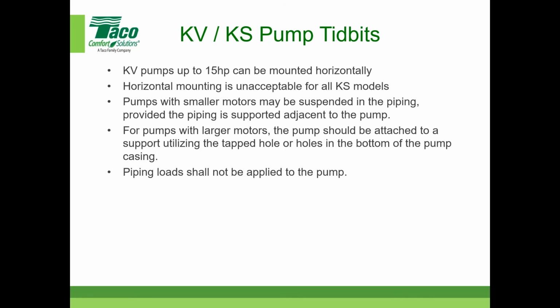Piping loads, common for all HVAC hydronic pumps and pumps in general, should not be applied to the pump. You need to pipe away and support it elsewhere. These pumps need to be allowed to move with the piping as it grows and whatnot. This is all spelled out in the instruction sheets, the I&O manuals, in much greater detail.